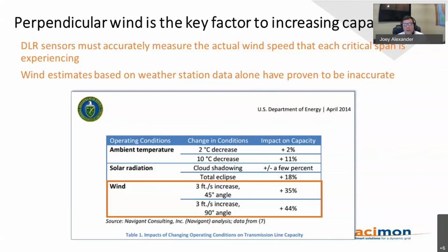Good that we're on this slide with wind. I'll stick on it for another minute, focusing on that orange square for wind, because when it comes to dynamic line rating, wind is key, especially the perpendicular component of the wind speed at the 90-degree angle. If you think about this from fluid flows and convective cooling, this is the wind that has the highest impact on cooling your line. So much so that just 1 meter per second of perpendicular wind can increase your capacity by almost 44%. That's a really positive thing.